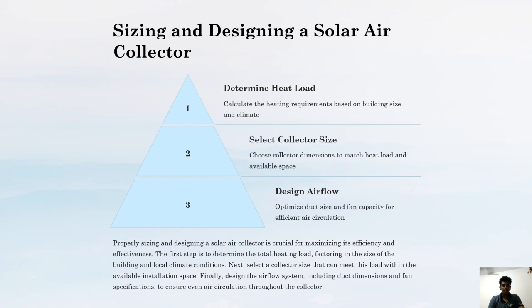Properly sizing and designing a solar air collector is crucial for maximizing its efficiency and effectiveness. The first step is to determine the total heating load, factoring in building size and local climate conditions. Next, select a collector size that can meet this load within the available installation space. Finally, design the airflow system, including dimensions and fan specifications, to ensure even air circulation throughout the collector.